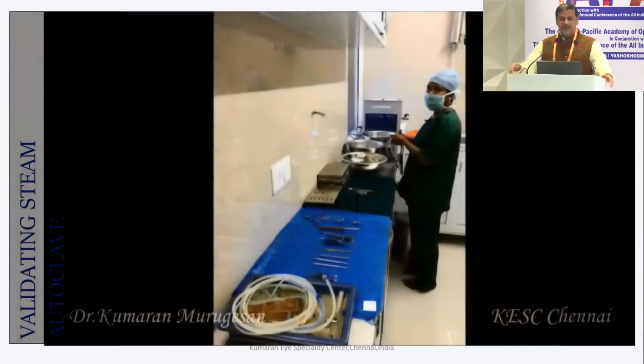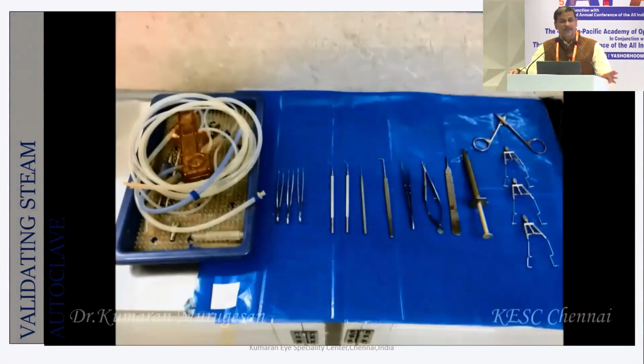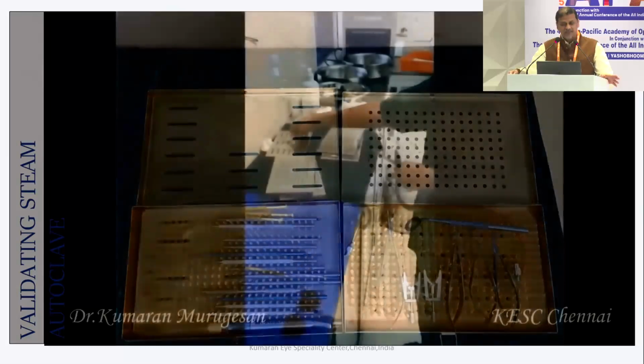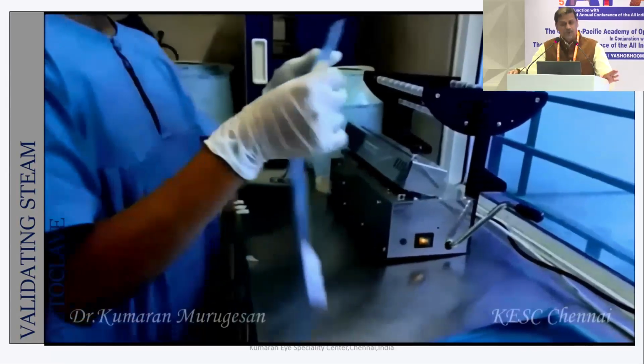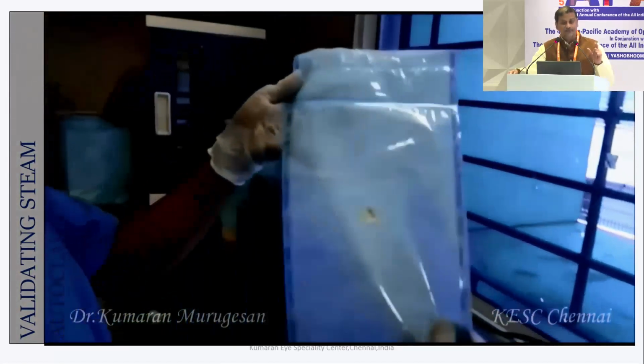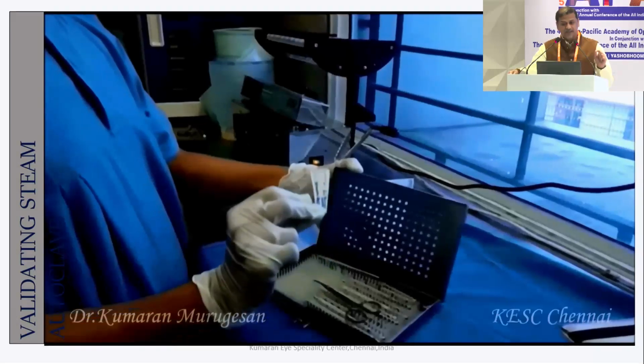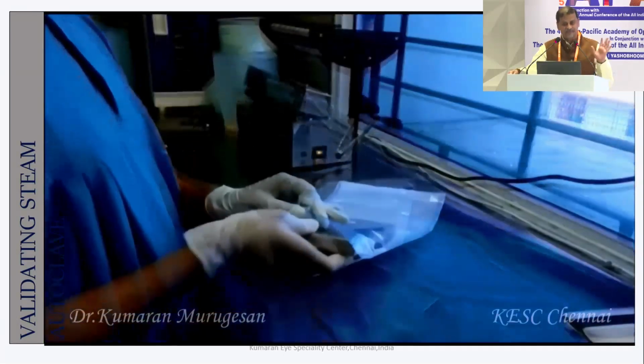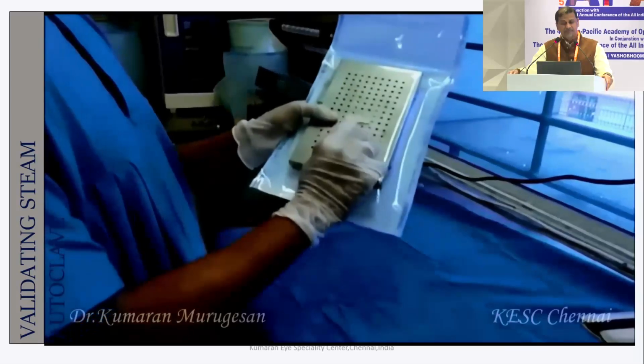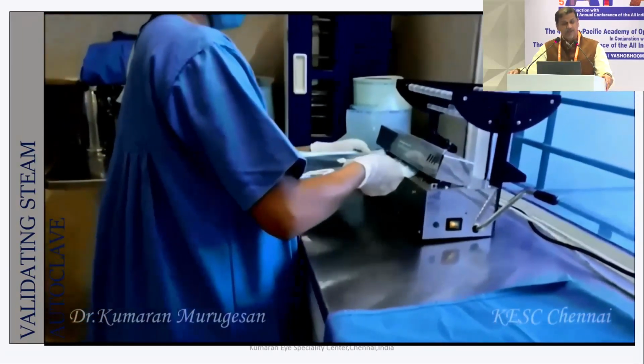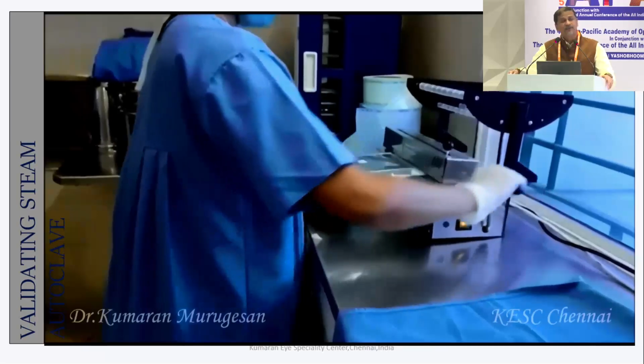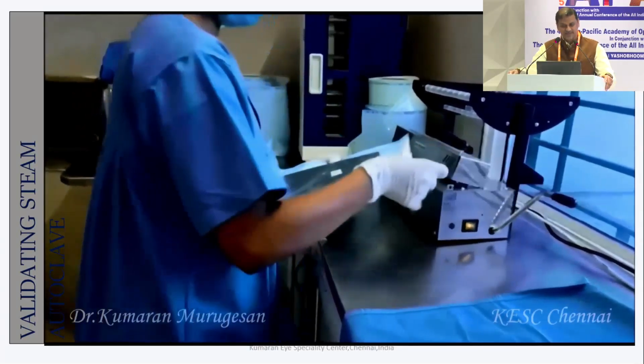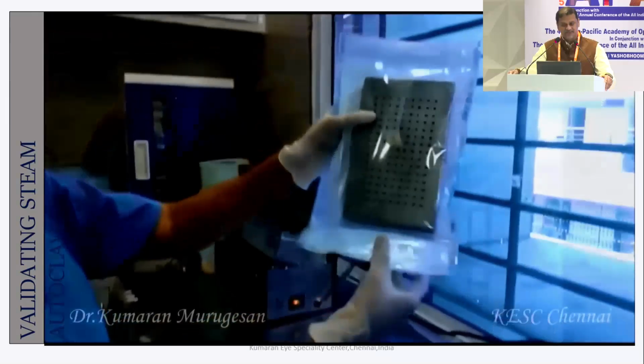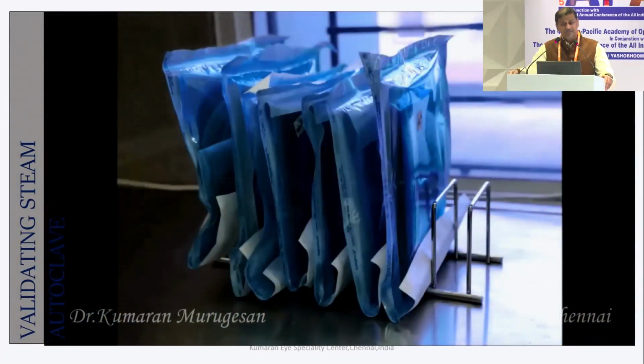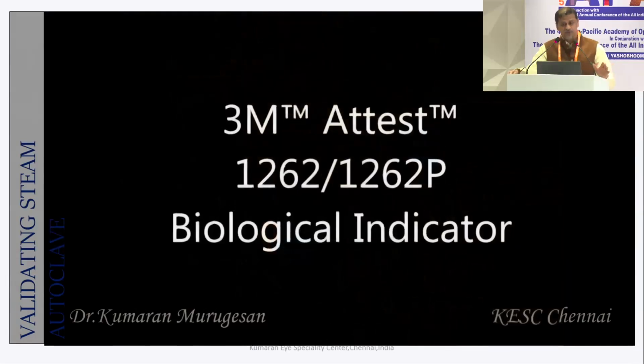So this is a small video which basically tells you how you really have to do all these indicators. I'm not going to talk about how these instruments are cleaned, that is beyond the scope of this topic. So once the instruments are cleaned, they are packed individually in different sets depending on the number of cases you have. Always use a medical grade sealer, because the seal is around 3 to 5 millimeters, and ensure that a class 5 integrator is placed in every set. And always use the plastic paper pouches and ensure that adequate space is available around each tray for the steam to penetrate inside, as shown by this paramedical staff.